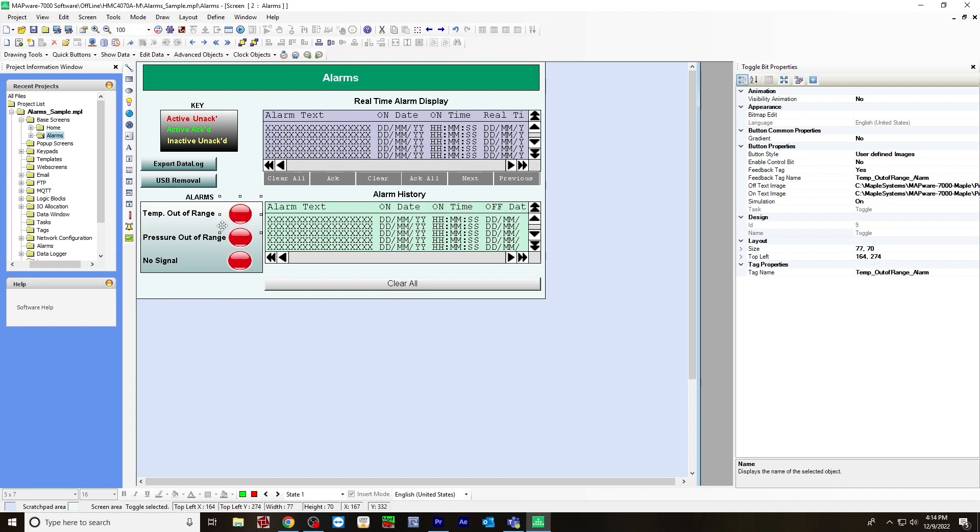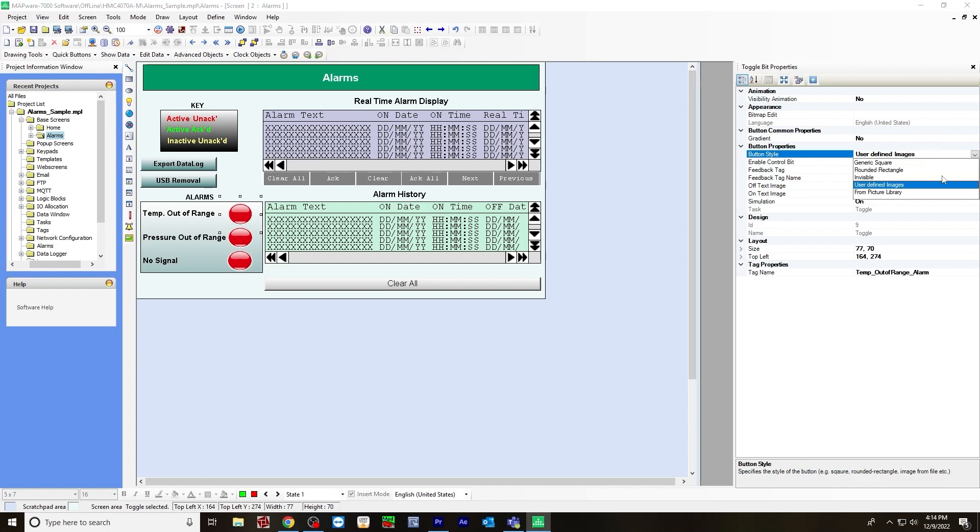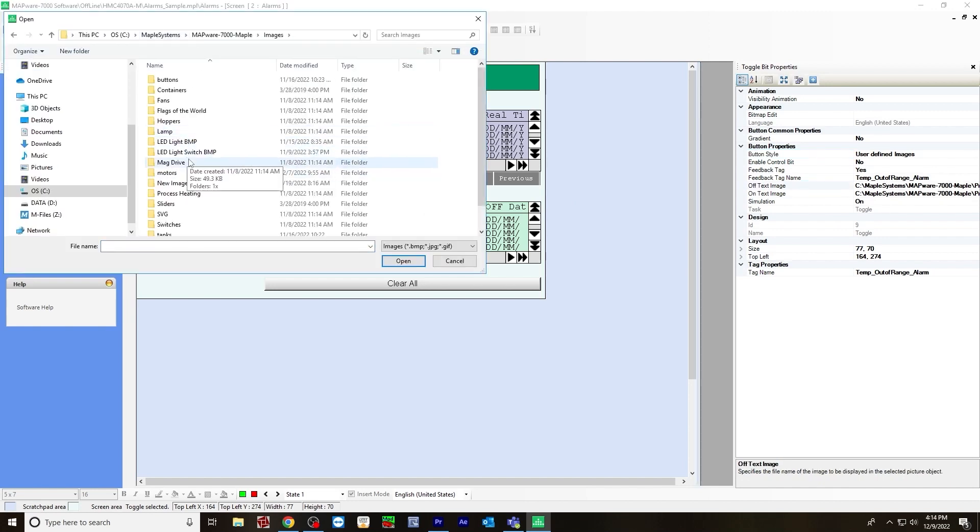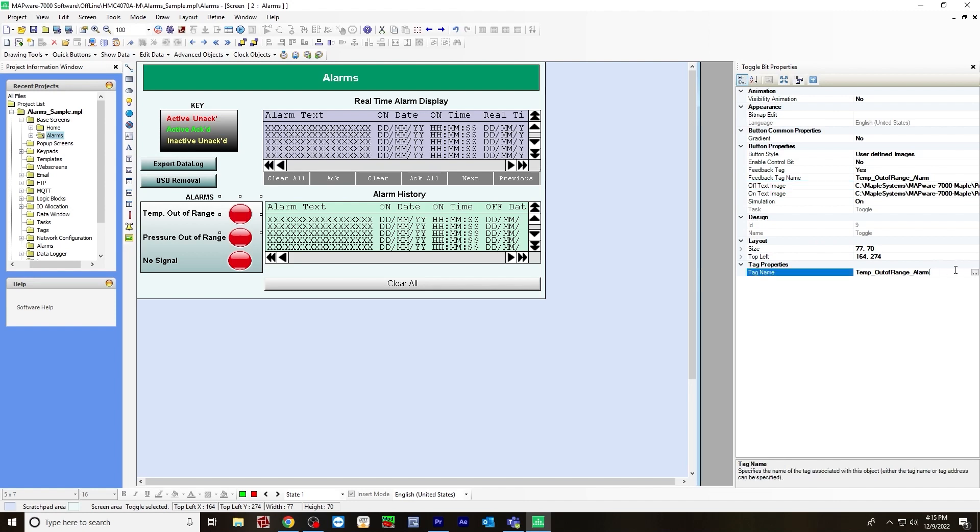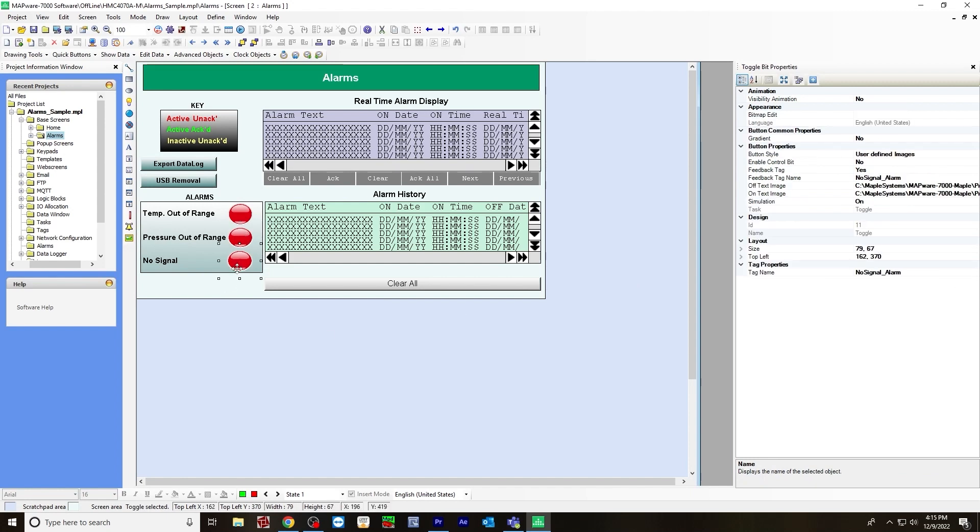These are not pictures you can find in Mapware 7000, they're not default. You have to use the custom picture option. You would go to button style and choose user defined images. For the off text, I chose to use an image from a folder on my PC. The off image is a black button, and the on image is the red that you can see here. For tag name, I selected the tag we created for the actual alarm - temperature out of range alarm tag name, and that's a bool.